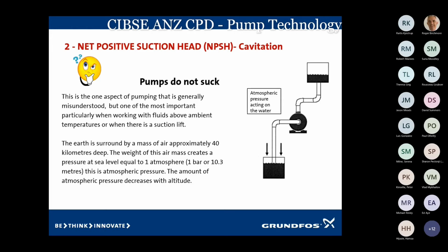No, a centrifugal pump will not suck. It's got to be filled up with water. It's got to be primed. So in this particular case, this pump is pumping from water below the ground. It has a foot valve in the tank, and then we fill the water from the pump all the way back down to the foot valve, and then we bleed it.